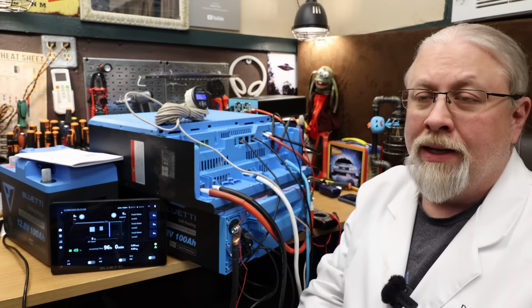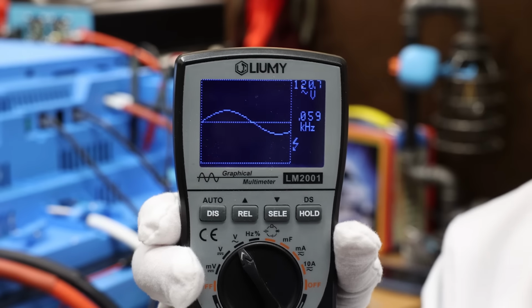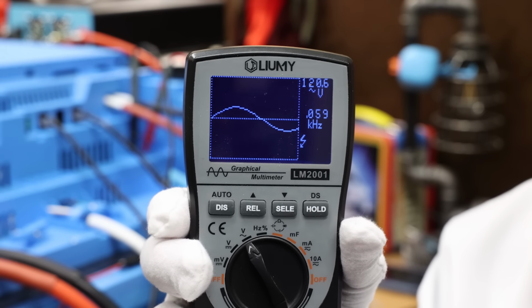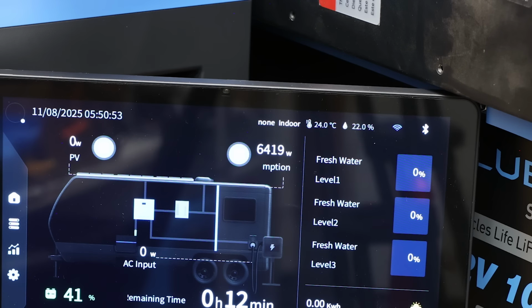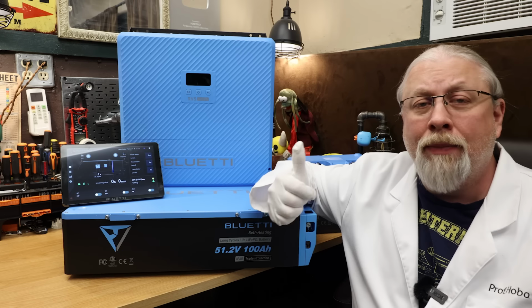Anyway, let's start the testing. Sine wave check under load: we scored 120 volts, 60 hertz, that's a pass. Inverter capacity test at maximum load: we're able to pull 6,400 watts for 5 seconds, that's a pass.